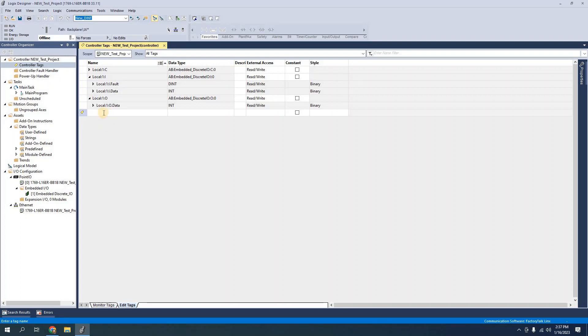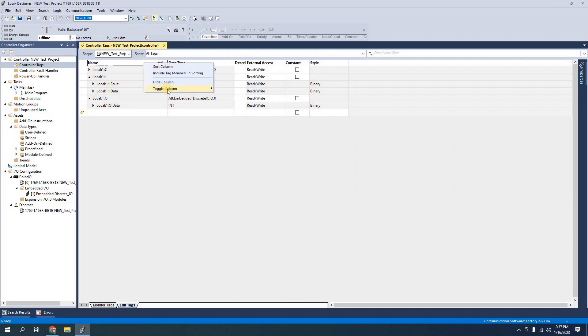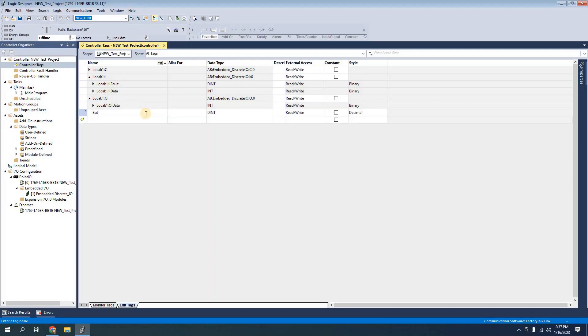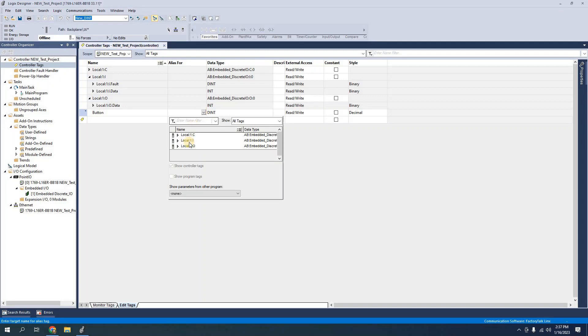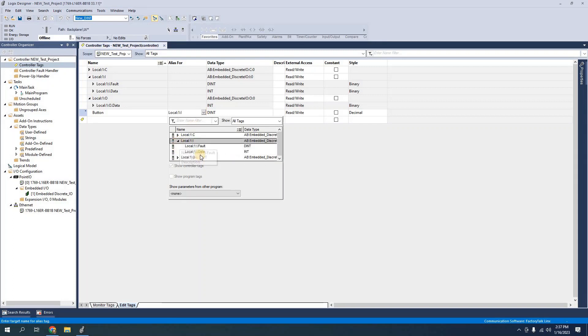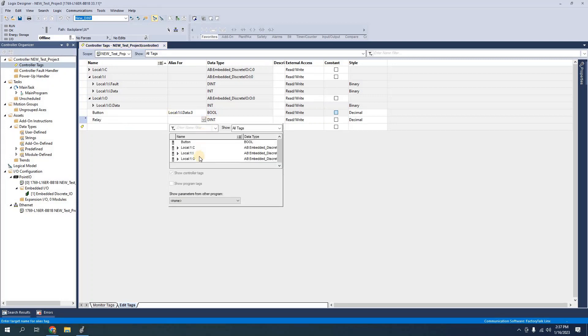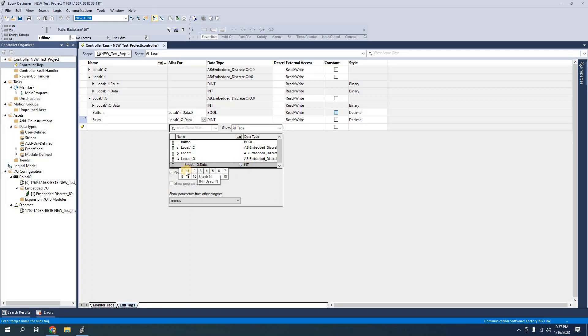But really quick before I do that I see that I have name data type. What I do not have up here is another column that's called alias for so I'm going to make sure that I check alias for and I'm going to create a button and the alias for I can either navigate down or I can remember the address but this will be the first data input terminal 0 and I'll do the same thing with a relay which will be local 1o data 0.